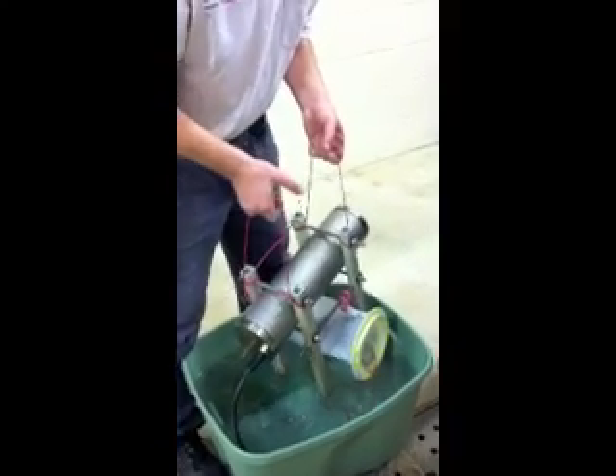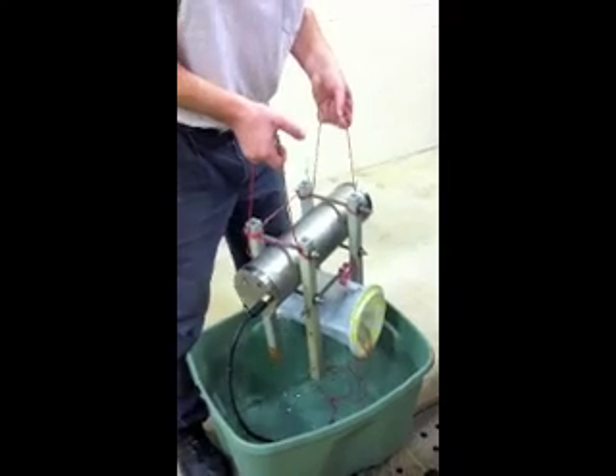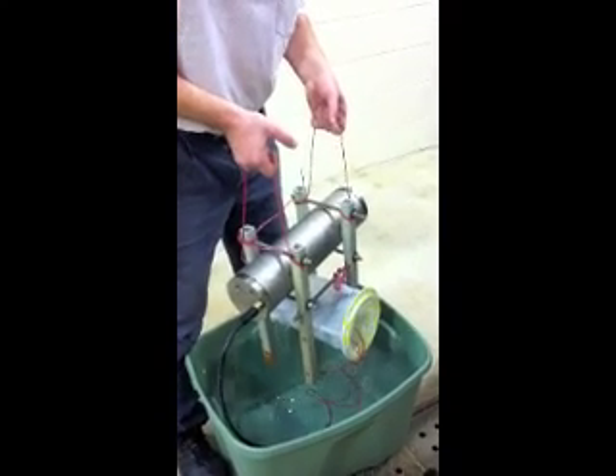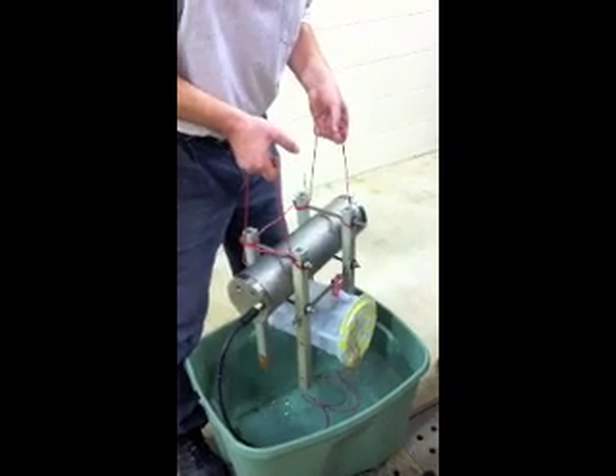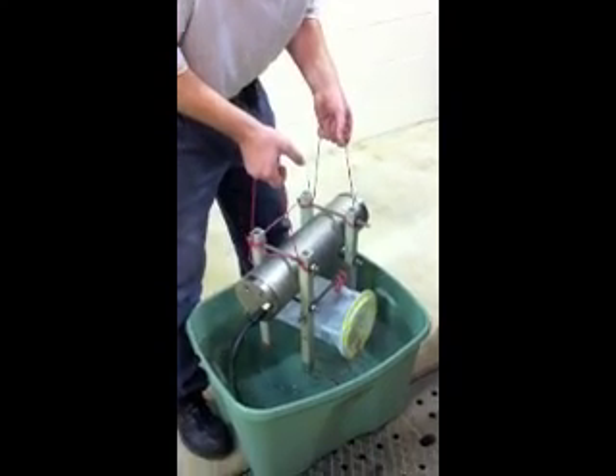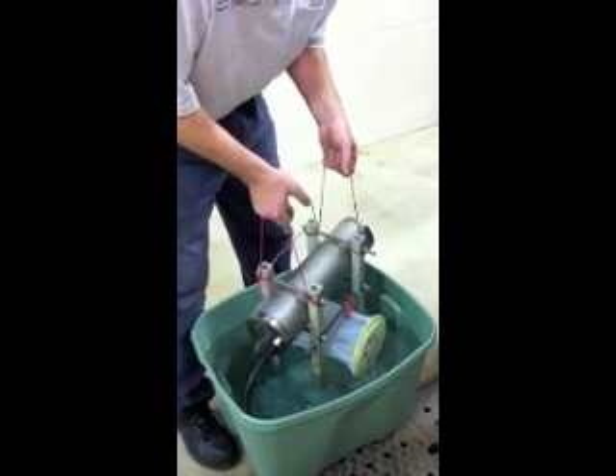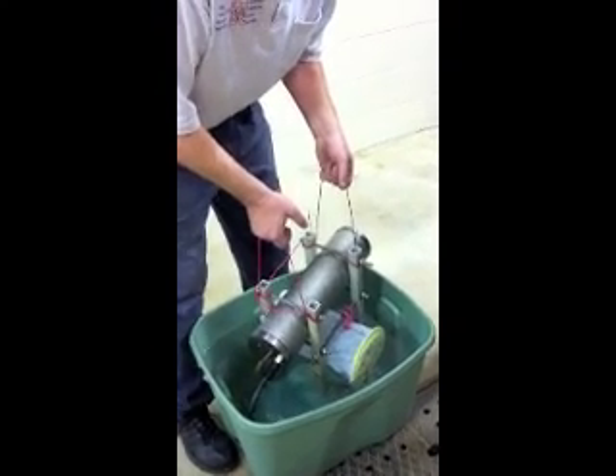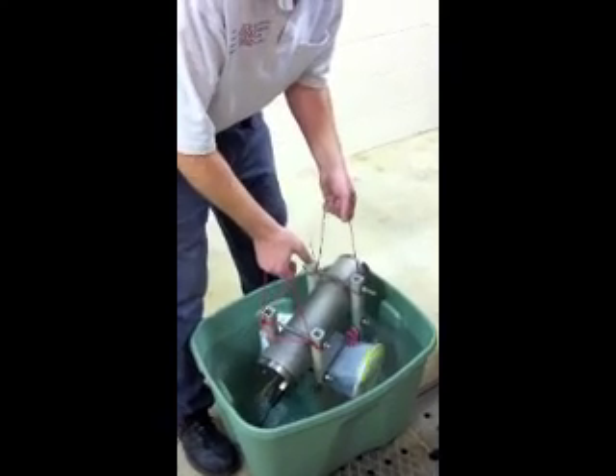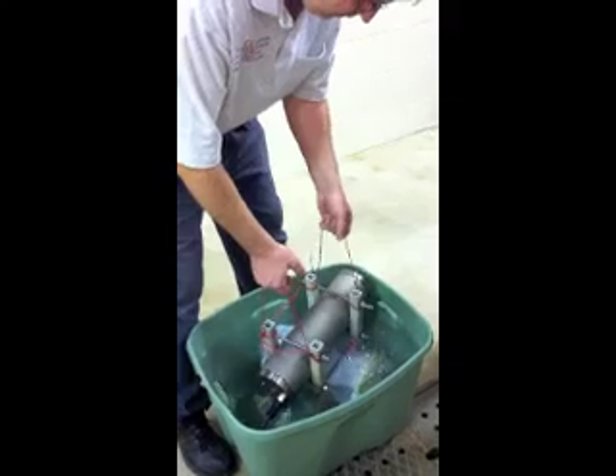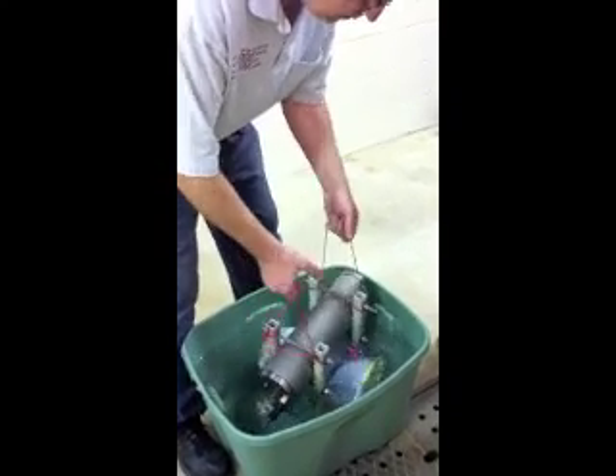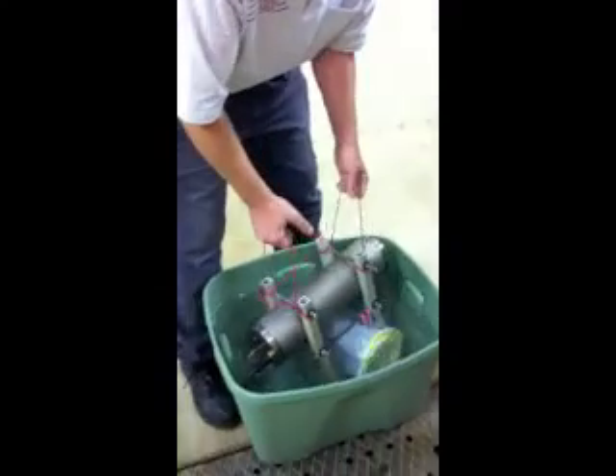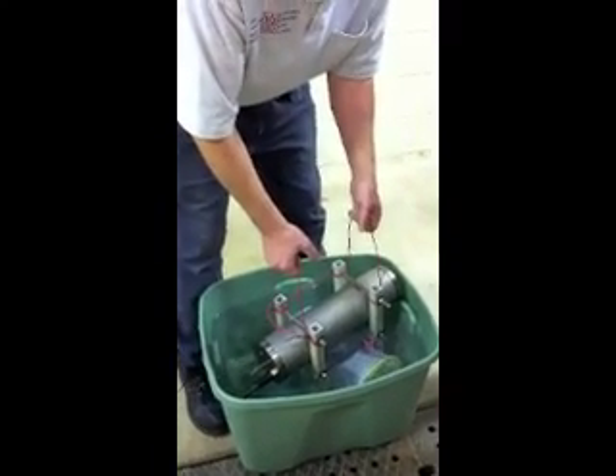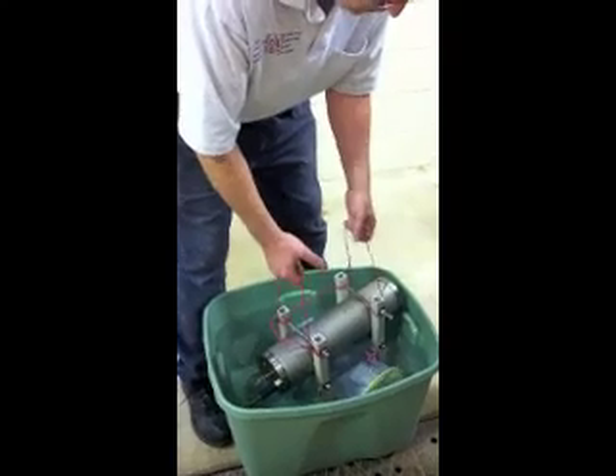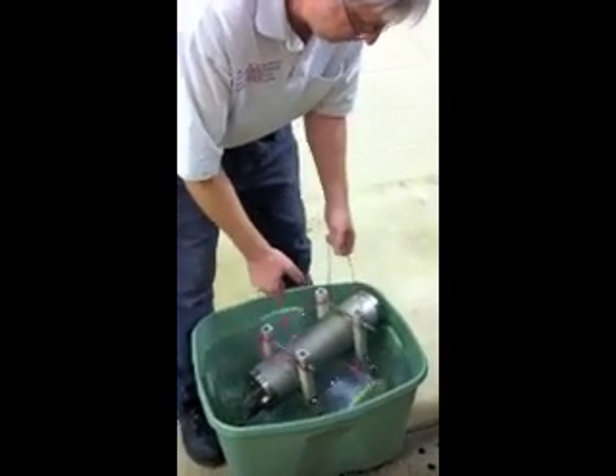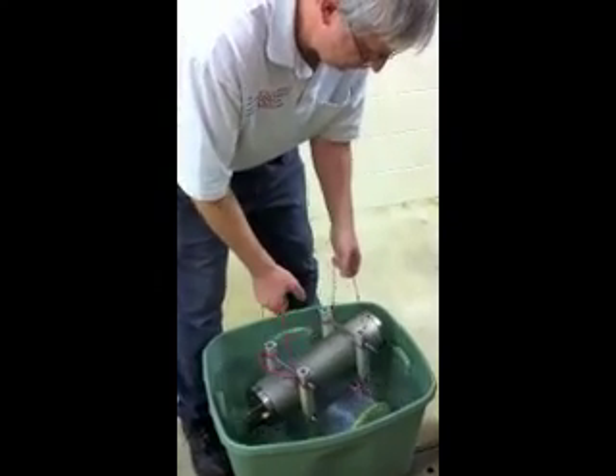This enables our sensor to completely drain itself of the previous water that it contained. Hold this for about 10 to 15 seconds. Then lower it back in slowly into the water. And after doing so, it's a good idea to implement a slight rocking motion. This is what we did the first time to enable the water to come back into the new water to replace the old water, and also for air bubbles to escape from within the sensor. And when this is done, this improves the response of the sensor significantly.